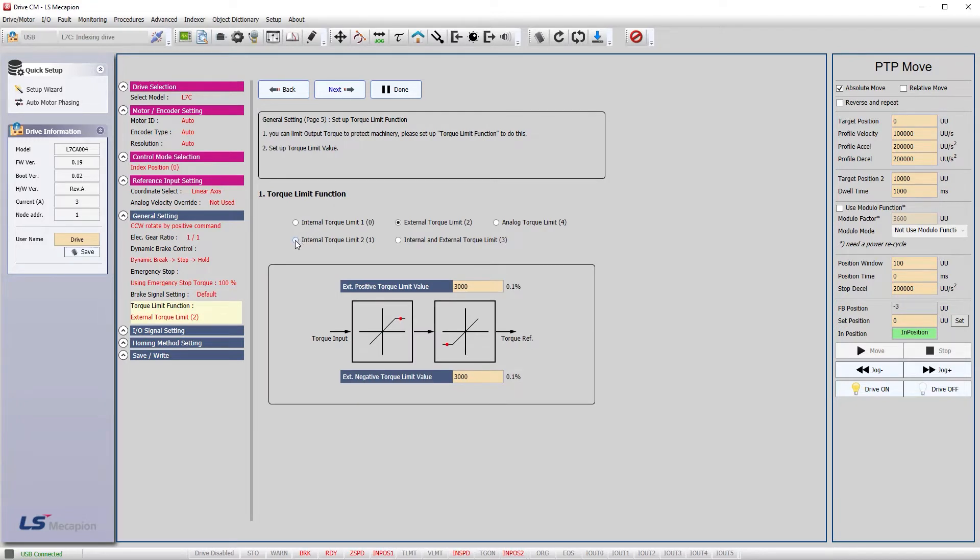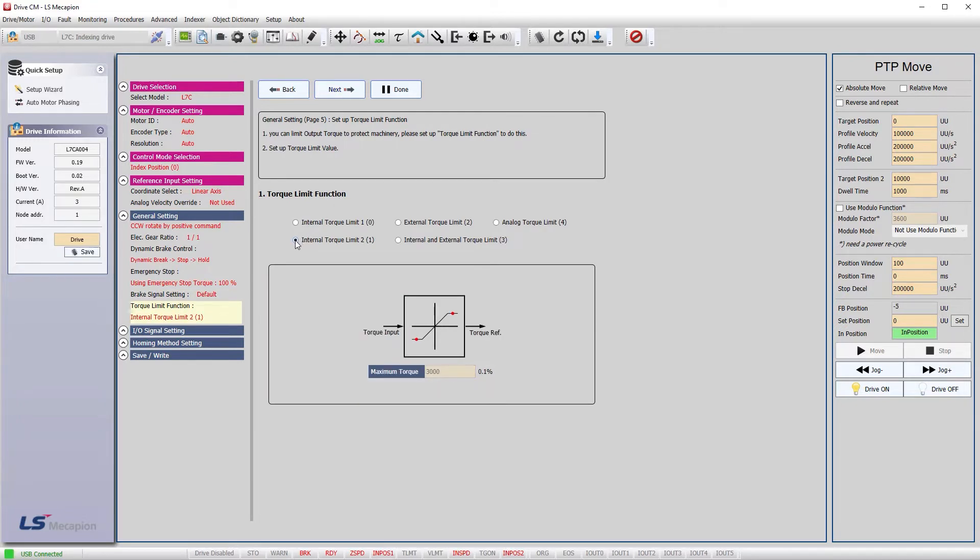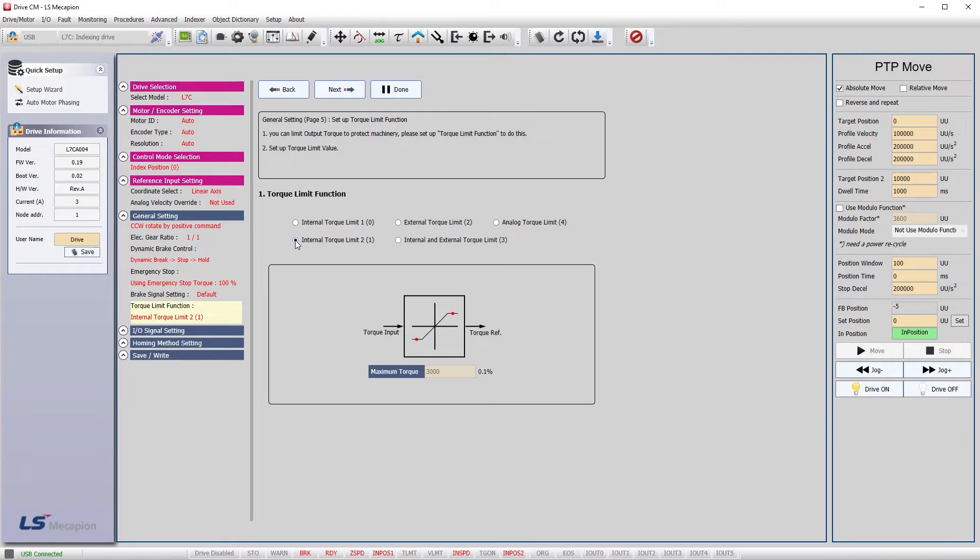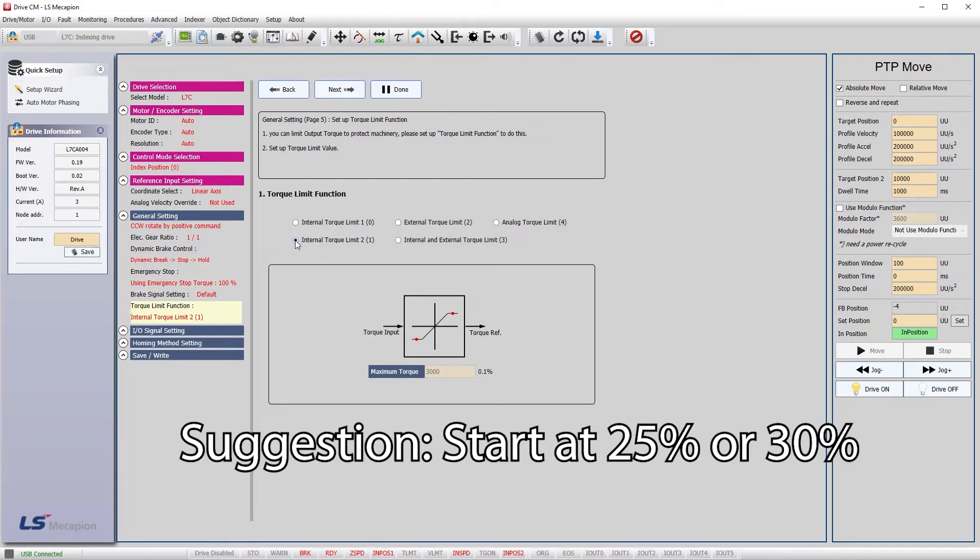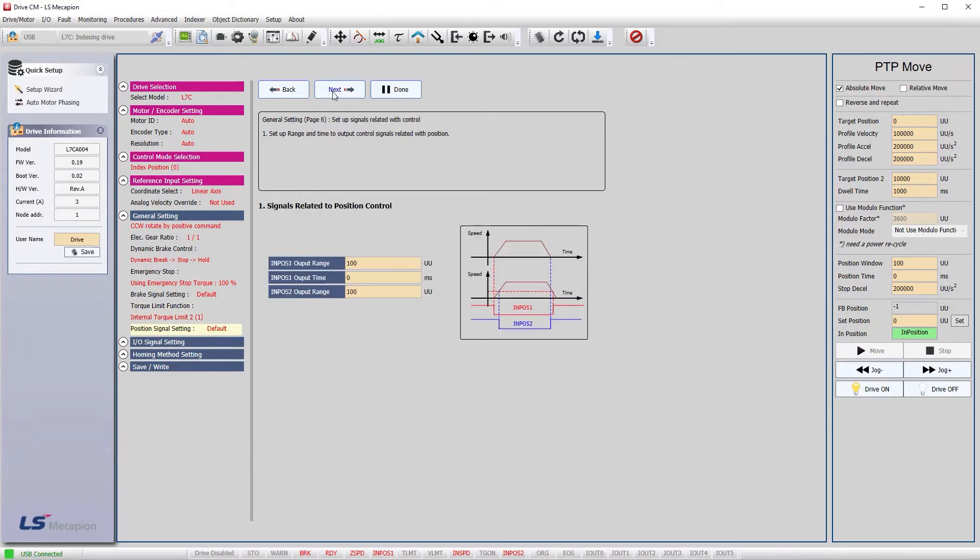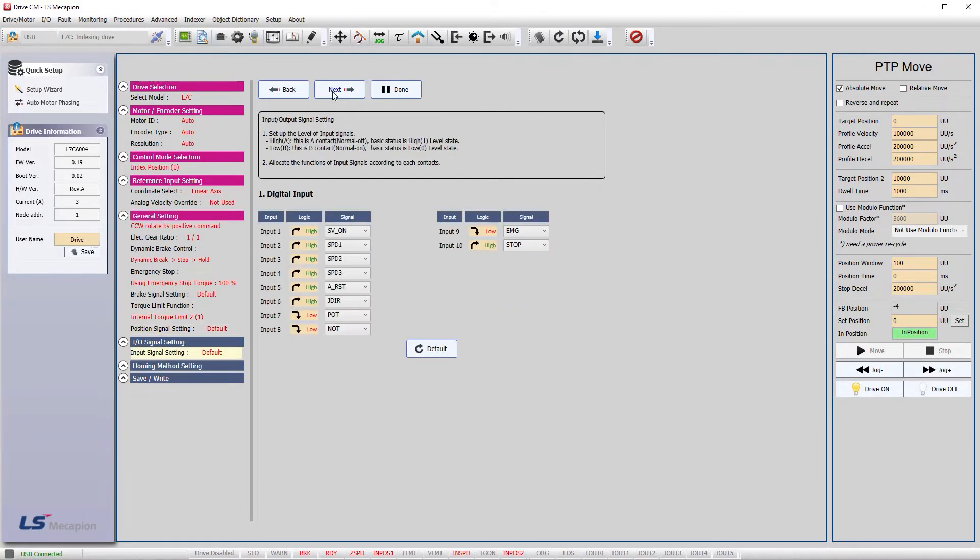I'll select the internal torque limit which is currently set to 300%. That's so the drive will limit how much torque can be applied if you slam the carriage into one of the end stops, a foreign object gets bound up in a power transmission, or if the material or product you are moving gets caught or stuck on something during the move. And normally, you'll want to set it to something gentle like a 25 or 30% torque limit when you first start out just in case something goes wrong.